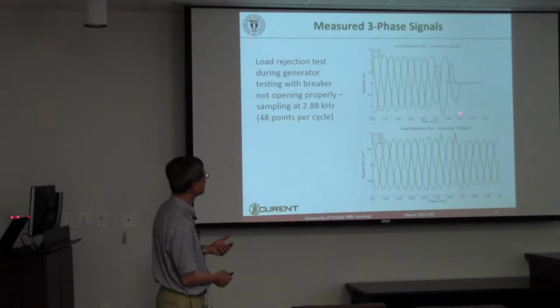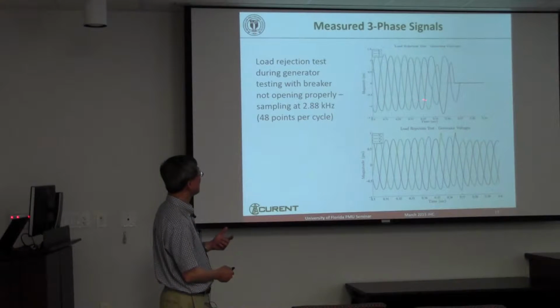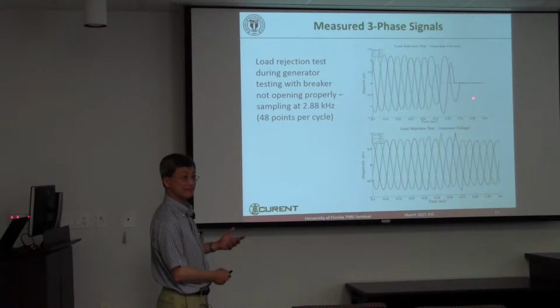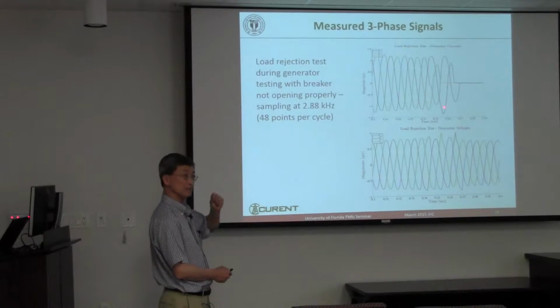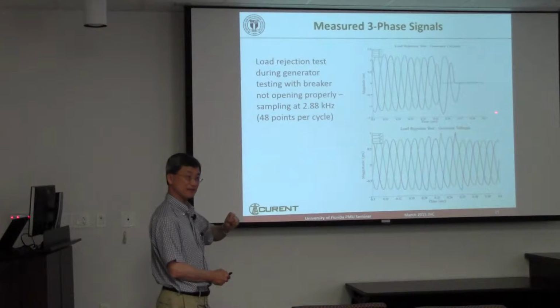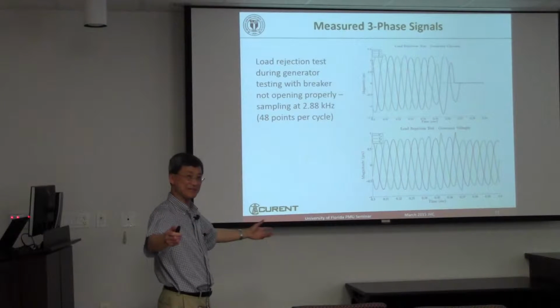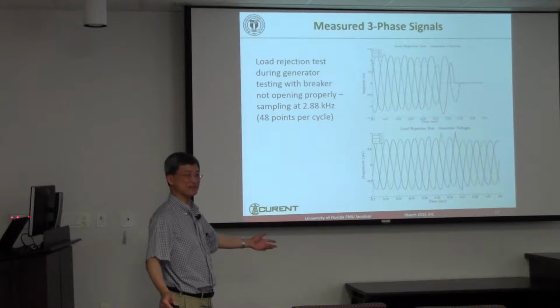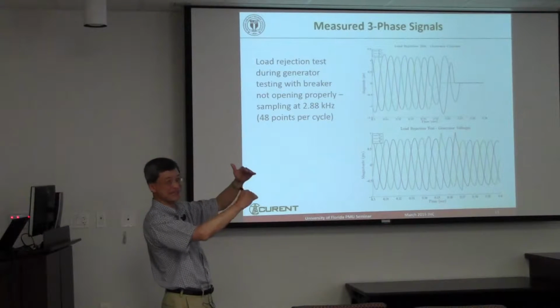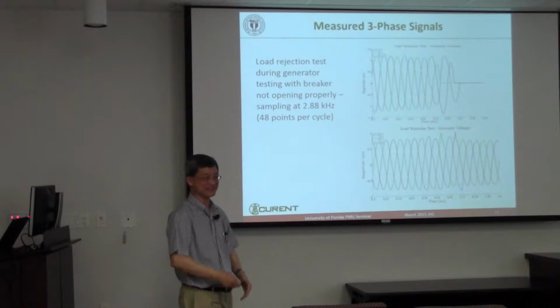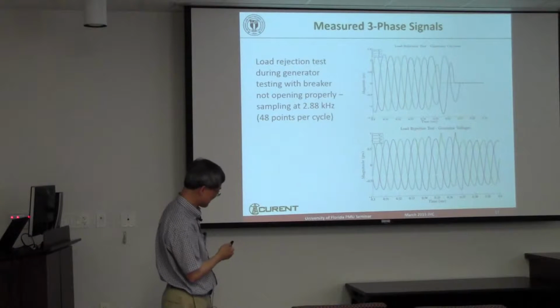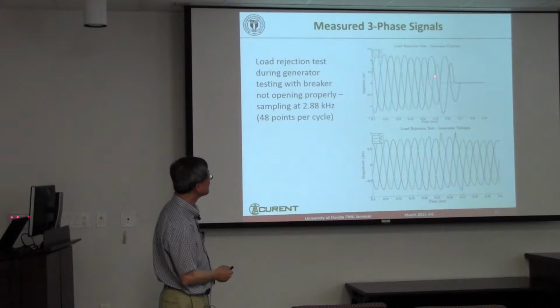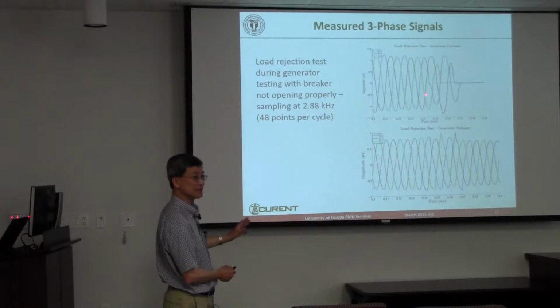Now this is a test — a load rejection test. Basically you pull the circuit breaker. When you pull the circuit breaker, do all three phases open at the same time? No, you can't, because you would create a lot of arcing. There would be a little gap, and you'd still have voltage and current across it. What happens is that circuit breakers can only open at zero current crossing, so that you can open them safely.